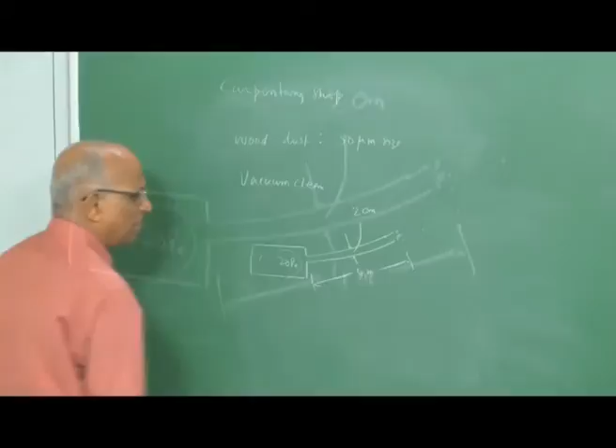Now, I want to find out the maximum rate at which the wood dust can be taken through the hose, such that an explosive substance is not formed here, because during the movement of the air and dust I could have sparks, and if there is a spark, the hose may just explode. I don't want that to happen. Therefore, I want to calculate the mass of the dust particles entering the hose, in kilograms per hour, or kilograms per second, such that an explosive concentration is not built with air in the hose.